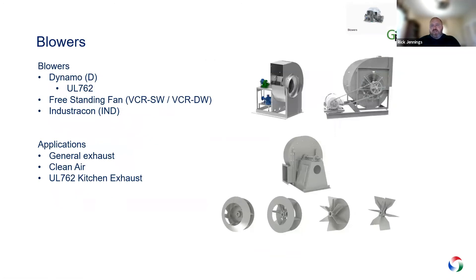In blowers, we start with a utility set — currently the Dynamo — which we're in the process of replacing. It's class one or less, mainly for places where you need a blower but don't need heavy-duty welded construction. The VCR comes in single wide and double wide, in flat blade and airfoil, available class one through four, and can come in various arrangements. The Industracon (IND) is our material handler series — for moving dust, sawdust, corn dust, or any highly abrasive environment.